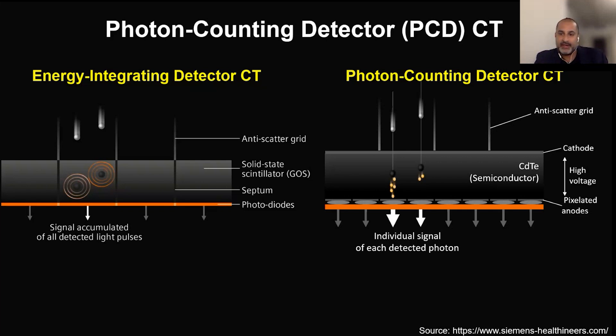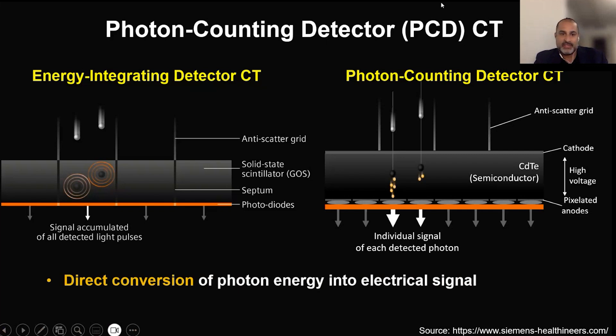So the photon counting technology people refer to as a better CT, but it's actually a totally new technology. This is something that's been talked about since before I started my career. When you look on the left, you see the energy integrating detector, which is the CT that everybody has and is used to. There are separations between the detectors, and what happens there is a two-step conversion. In imaging, anytime there's more steps, you lose some of the imaging data and you get increased image noise.